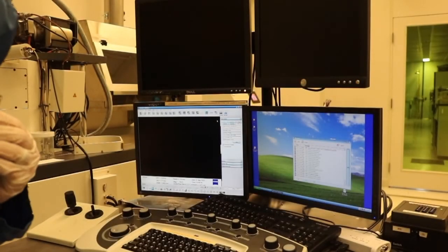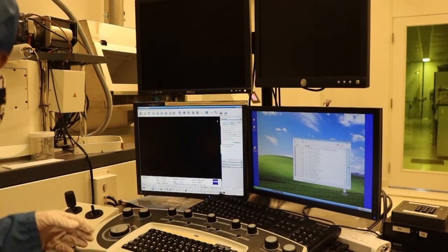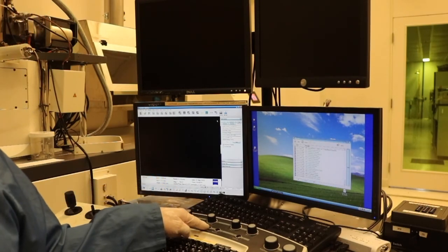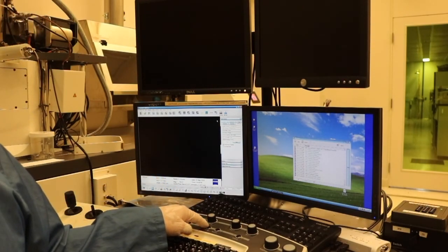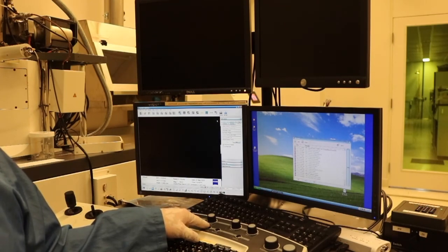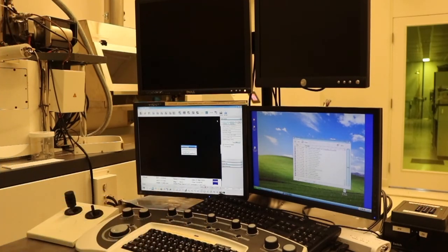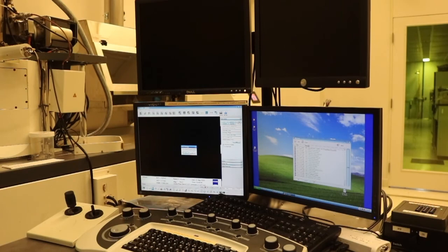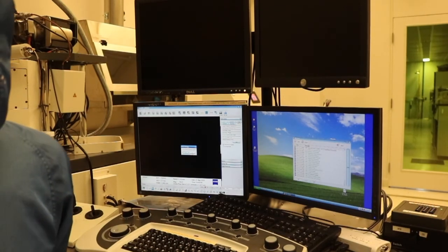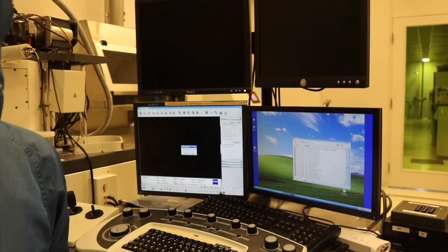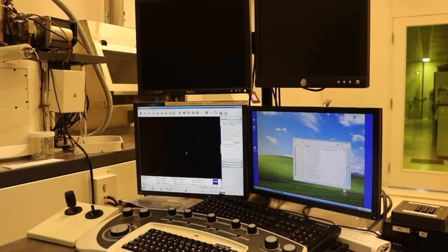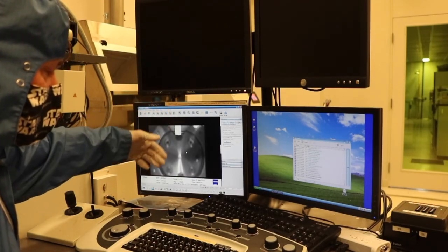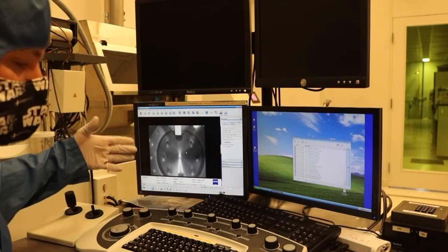At the microscope, we can come in to the hard control panel interface, and there is an exchange button located right here. This exchange button will actuate the exchange procedure for loading your sample. In pressing that button, you'll receive a message on the display which suggests, do you want to vent the chamber, yes or no? The ability to say no would be if you accidentally hit that button. It'll turn on the infrared chamber scope, move the stage to a safe position, and then stop the pumps.